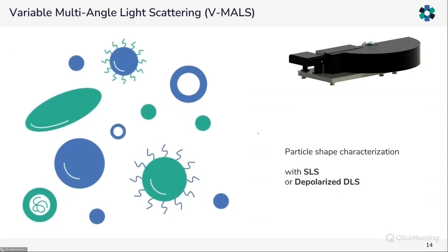The V-MALS technique is also used to characterize particle shape using static light scattering by determination of the form factor. One can also use depolarized light scattering by introducing polarizers into the system, which is an available option. With this, one can characterize dense spheres, hollow spheres, fully loaded or unloaded carriers like AAV capsids, functionalized particles, or anisotropic particles such as ellipsoidally shaped ones.